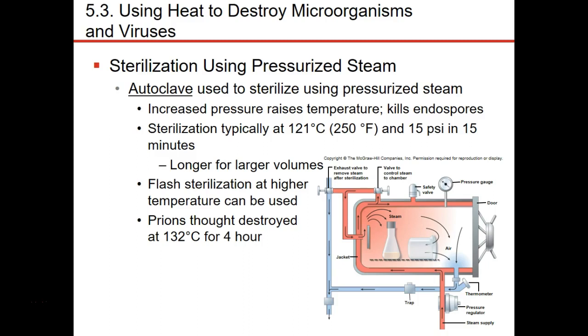The one mechanism using moist heat that does sterilize is pressurized steam, which is what our autoclave does. The autoclave uses pressurized steam to increase the temperature to about 121 degrees Celsius (250 degrees Fahrenheit). Increasing the pressure causes the temperature to rise above boiling, and leaving it there for 15 minutes will kill endospores. In our lab, we heat to 121 degrees Celsius and keep it there for 30 minutes to make sure everything is killed off.